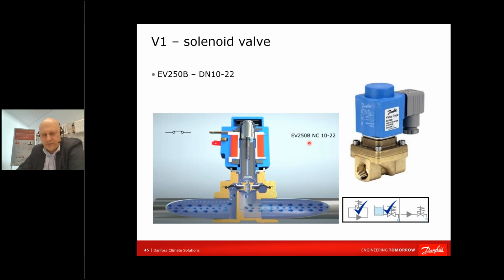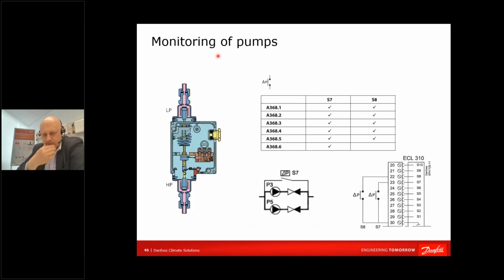A solenoid valve, which we might use for the fill-up. You're providing electricity to the valve. The valve is opened if it was normally closed. And here you go. For the fill-up of a system, you need a small valve. You do not need a huge valve, because to fill up your system you will need to spend 10, maybe 20 liters, and that is it. If you would like to use that connection for feeding the system completely with fresh water, you can do it manually, no big things.